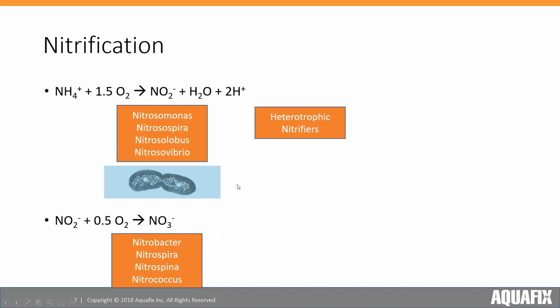We also have some ammonia that will be removed by heterotrophic nitrifiers. The next step in the process, the conversion of nitrite to nitrate, we primarily thought this was done through Nitrobacter, and that is still maybe true, but nitrifying bacteria are becoming increasingly better characterized. And there is increasing evidence that Nitrosomonas and Nitrobacter are not the primary nitrifiers in wastewater activated sludge. Different nitrifying bacteria tend to specialize to different conditions, so different wastewater plants tend to have very different populations of these nitrifying bacteria.